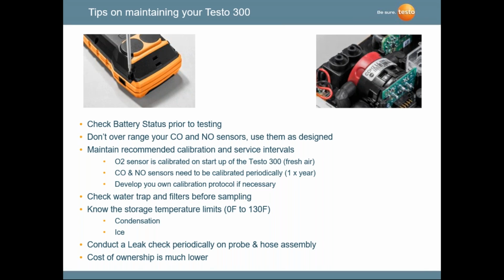Don't overrange your CO sensor. I showed you a little bit of how to determine a level of CO that's below the range of the CO sensor and set that range to 1,000 to 2,000 ppm CO.